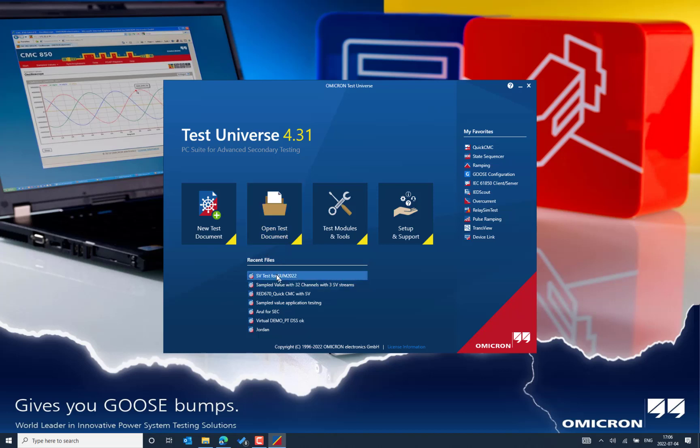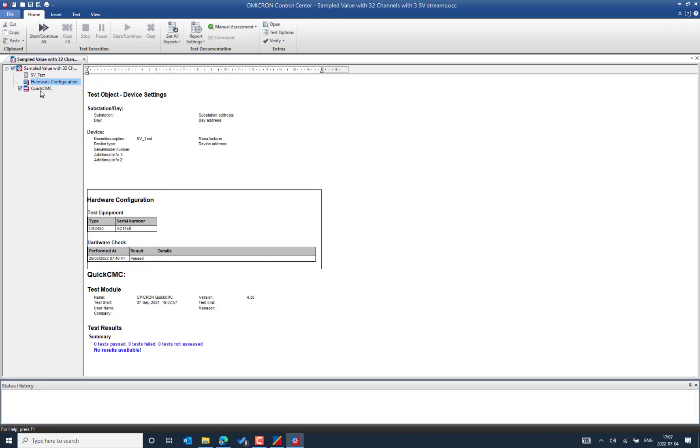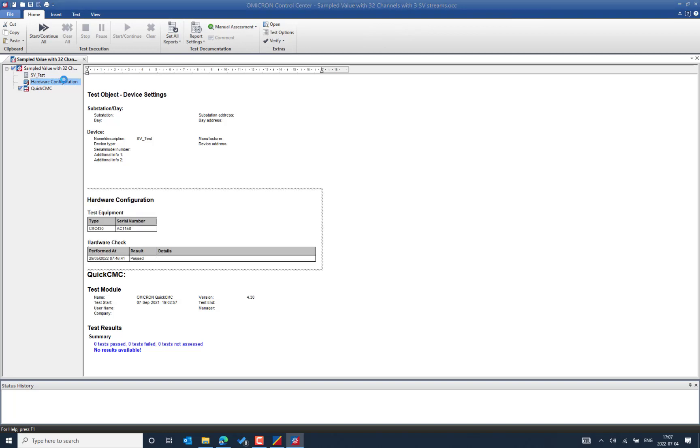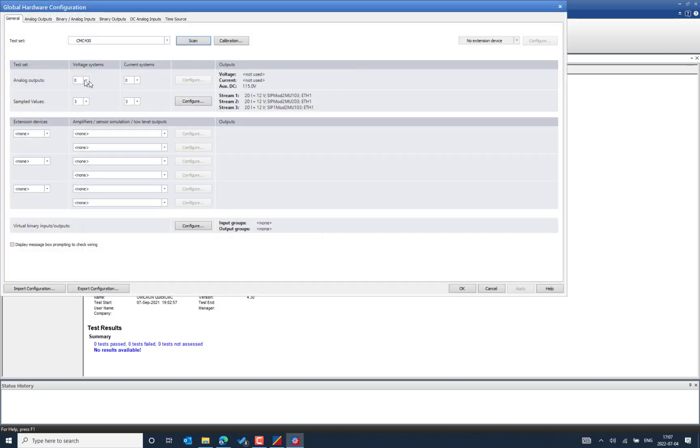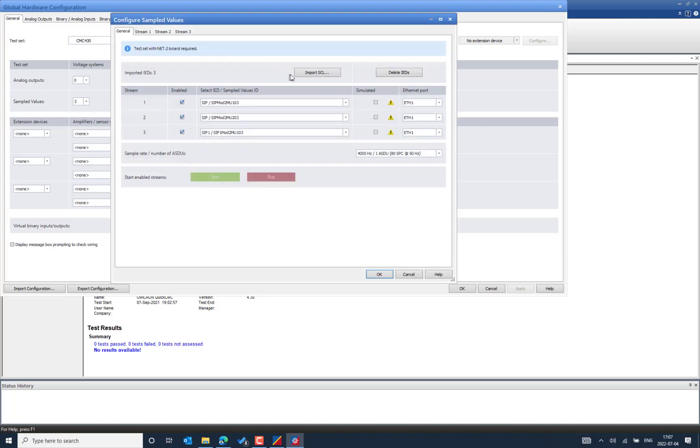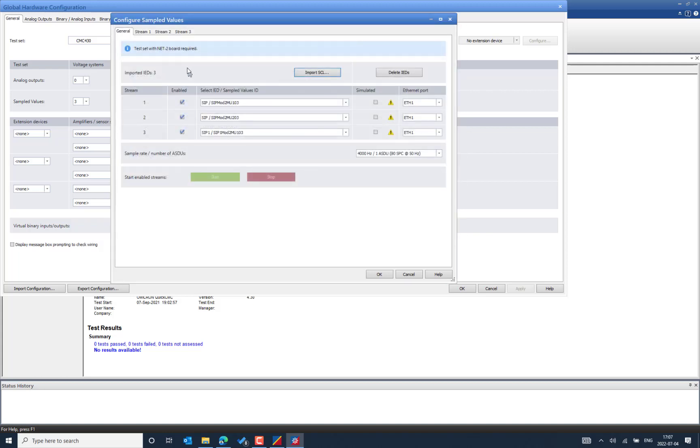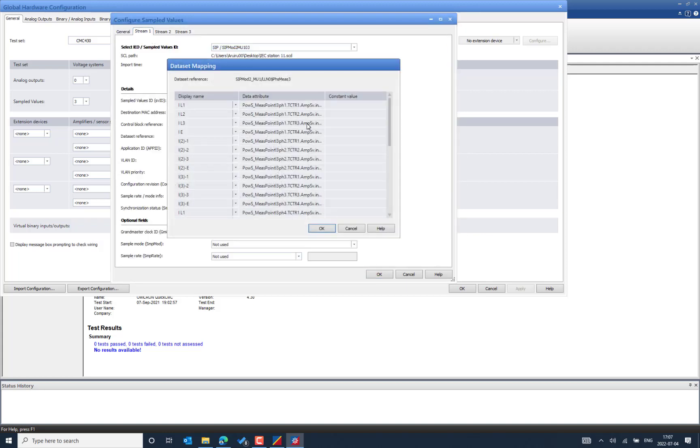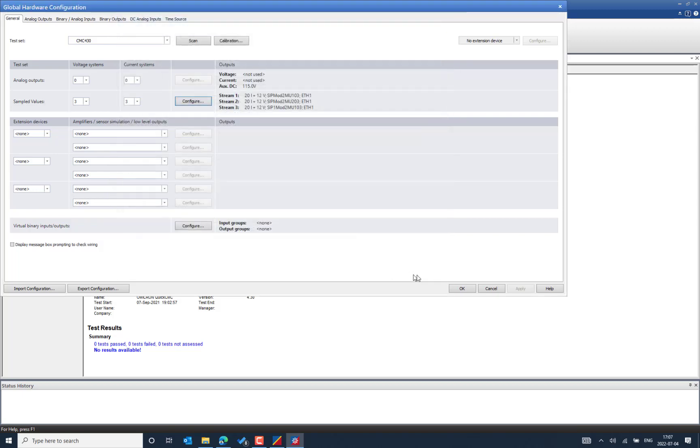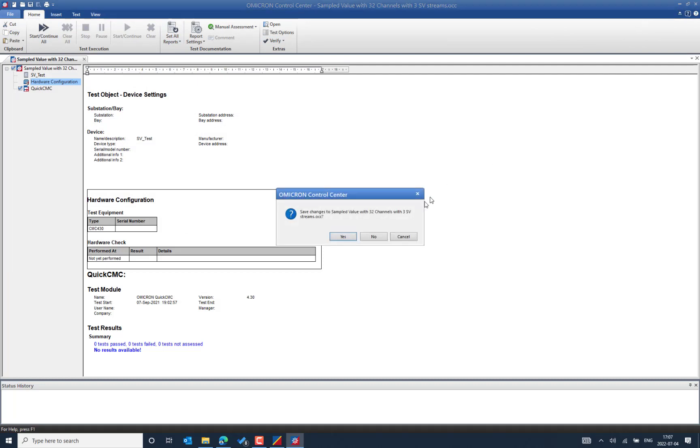And you can run the different test case steps that you have created already with the previously created OCC file. And you will be able to see all the information that is defined, for example in this case the hardware configuration has the sample value control block mapped for the different data points that you can see from the stream one and the data set mapping already done. This is able to reuse the previously created OCC file and the different templates.